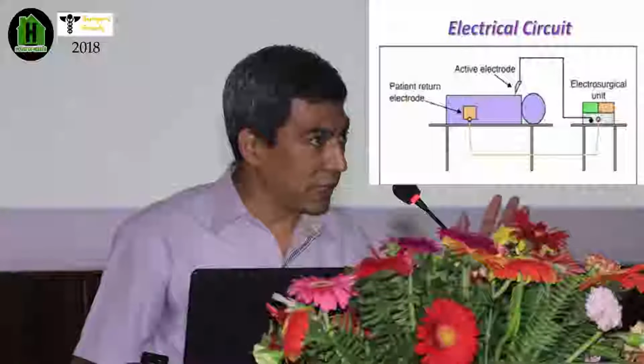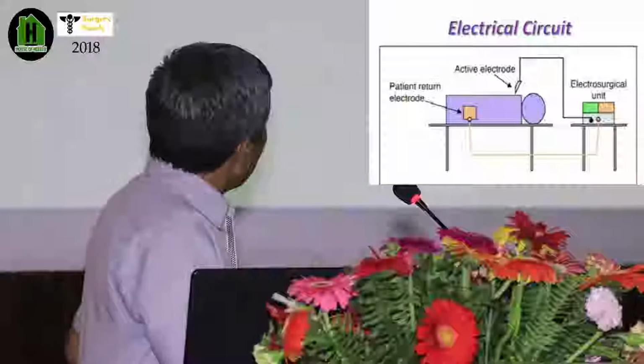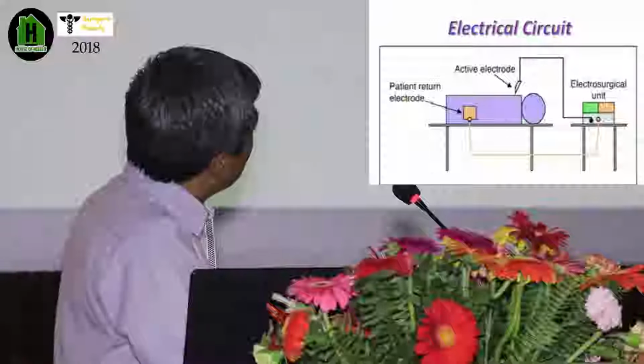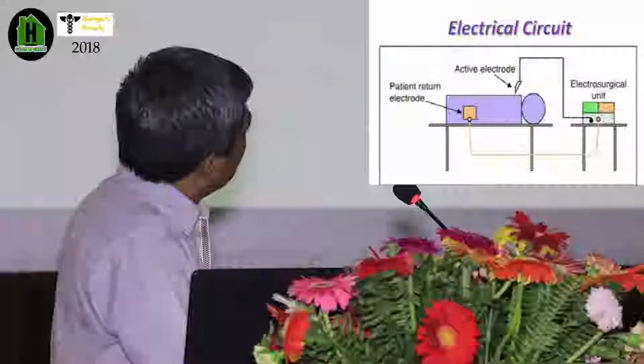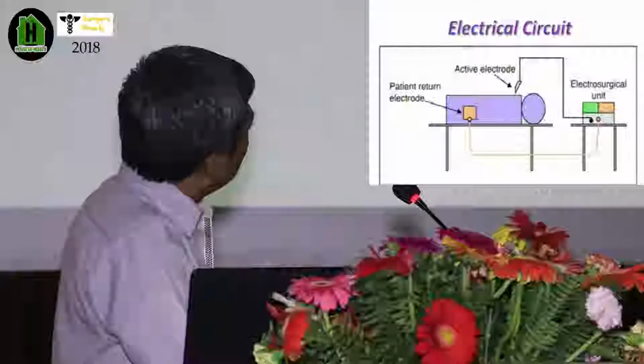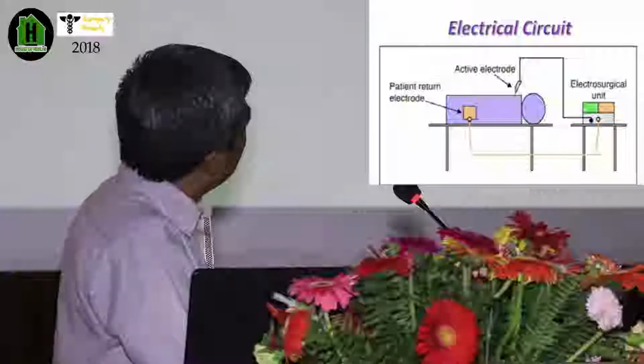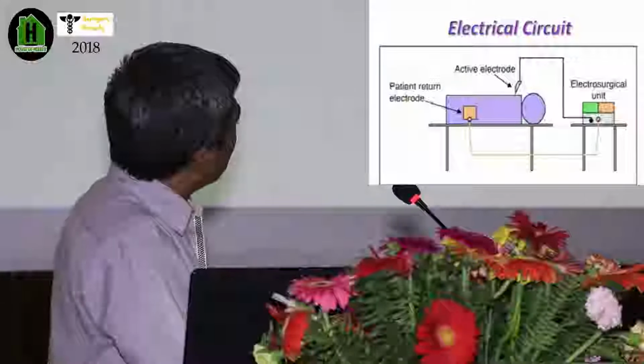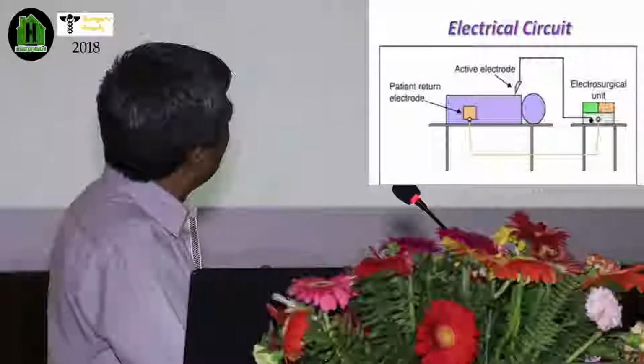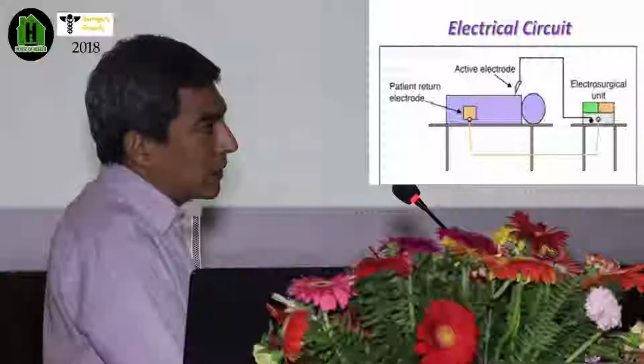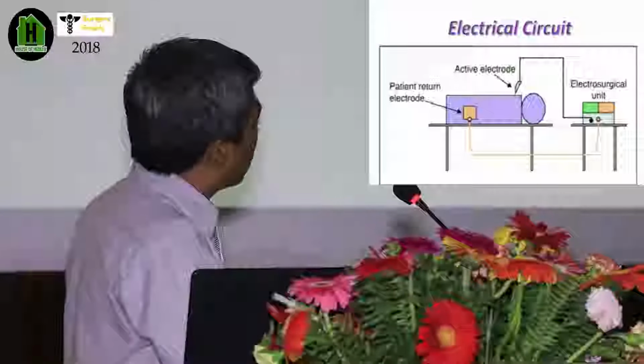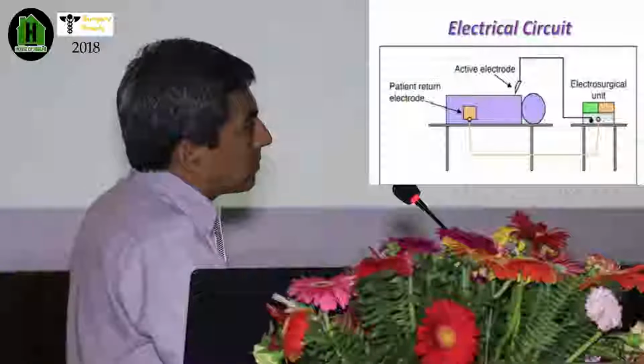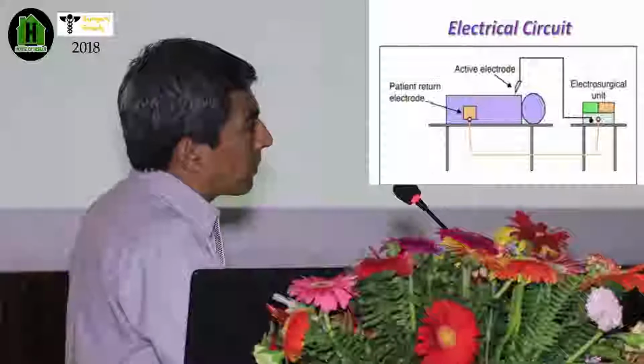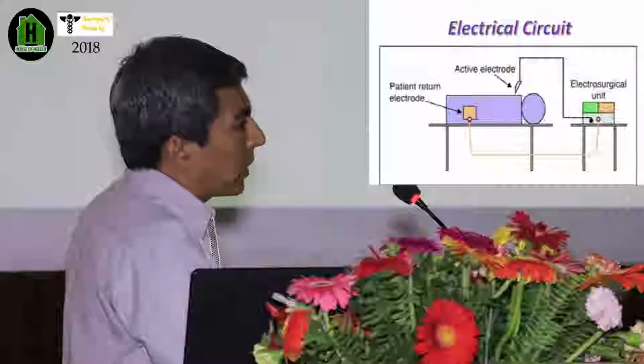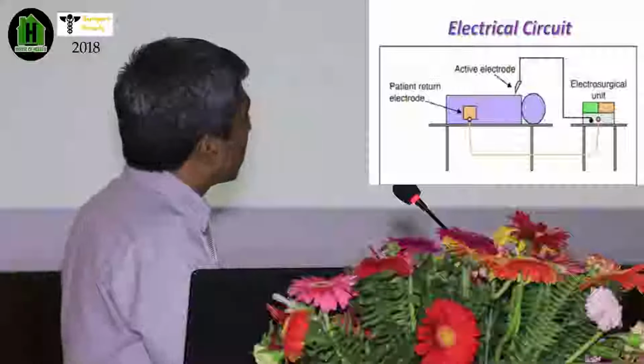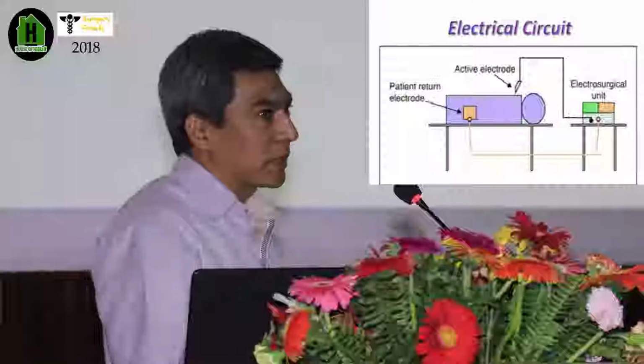The principle of the electrical circuit in radio frequency electrosurgical units is here in the picture. There is the patient, and the electrosurgical unit generator is here, with the active electrode going there. Once the current is passed through the tissues, all the electrons are collected by the passive electrode and then transmitted to the generator again. The circuit has to be completed, otherwise it won't work. If there is some short circuiting from patient to earth, then it won't work. We will be having a disaster then. So we must think about all those things, though it looks very minor. That's why I think this topic is kept here.